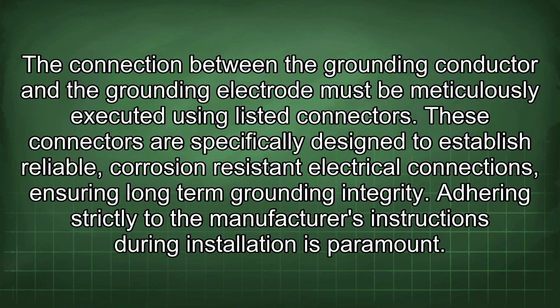The connection between the grounding conductor and the grounding electrode must be meticulously executed using listed connectors. These connectors are specifically designed to establish reliable, corrosion-resistant electrical connections, ensuring long-term grounding integrity. Adhering strictly to the manufacturer's instructions during installation is paramount.